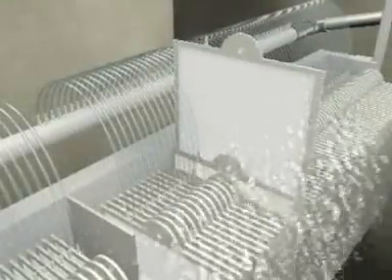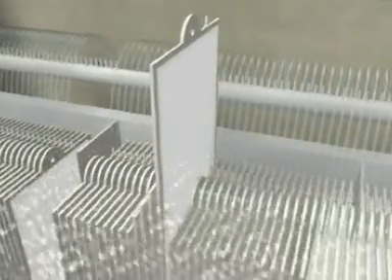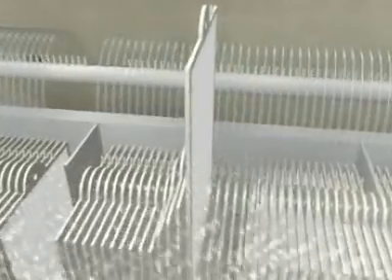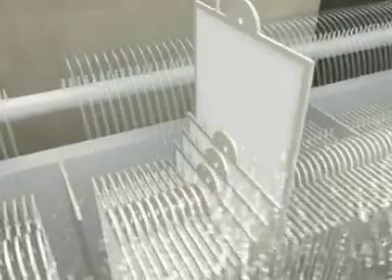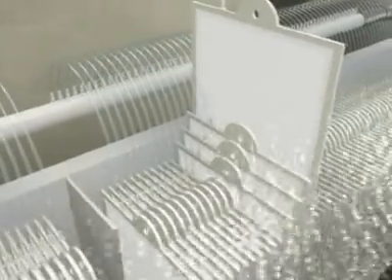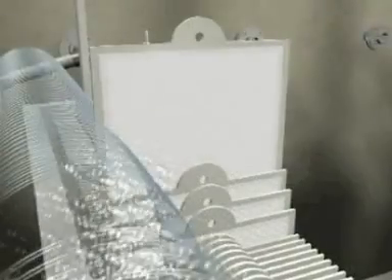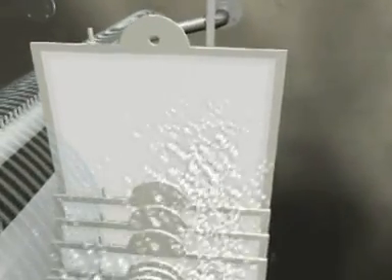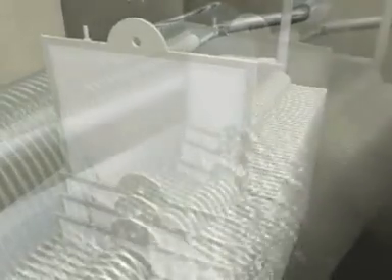The panels are held 7 mm apart, the principal advantages of this design being that the membrane panels do not touch or abrade each other, so increasing membrane life, and are not clogged with hair or fibres, so reducing maintenance costs. This process has none of the fouling problems of some other membrane systems, which require frequent manual intervention and downtime for remedial action. The flat sheet design therefore achieves the maximum performance, efficiency and longevity, with the minimum of operator intervention. The integral part of any membrane bioreactor plant, irrespective of its size, is the membrane panels.